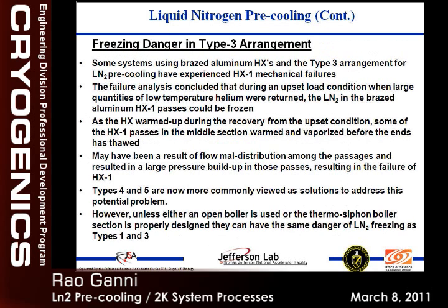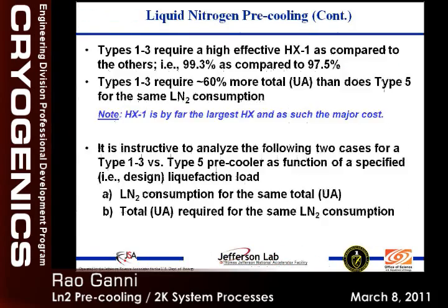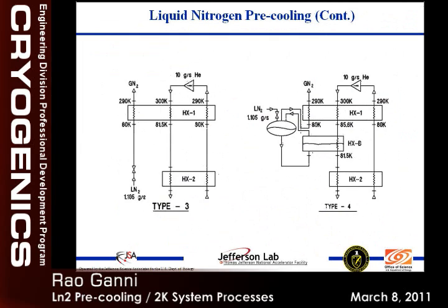There is another issue with these various nitrogen pre-cooling arrangements, when we use type 3, where we inject nitrogen here and we have the helium. Say, for example, we had a huge quench from the magnet, and you have a lot of low side flow coming. So this temperature will drop very quickly, and what will happen is it will freeze the nitrogen. Because if it falls to say 20, 30 Kelvin here, which is not uncommon on a huge bunch, this will freeze the nitrogen here.